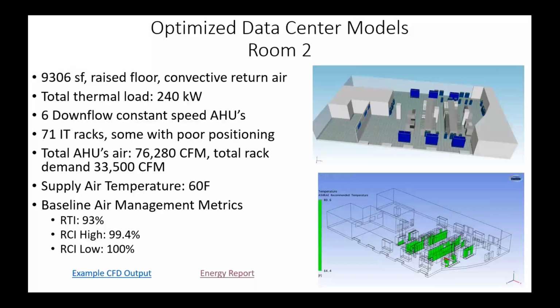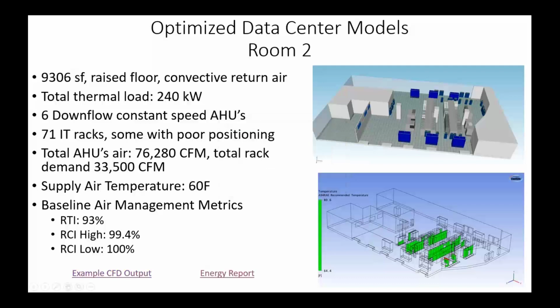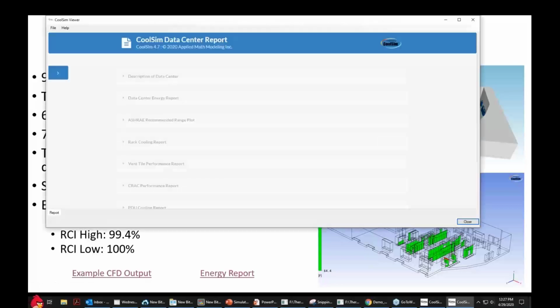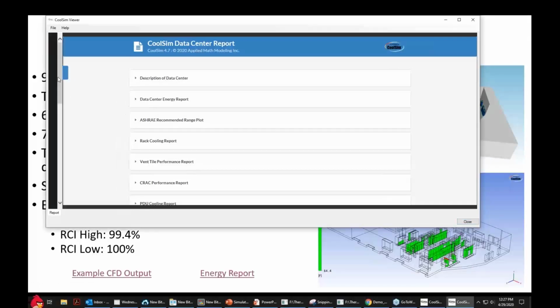So here is room 2, again, used containment. You can see the containment there, boxed in the cold aisles in this case. That was the easiest thing to do. This one, I couldn't get RTI quite as high and I couldn't get temperature quite as high because in this particular data center, there are a couple of funky things about it. It's got some side breathing pieces of equipment over here on the right that are causing some issues.